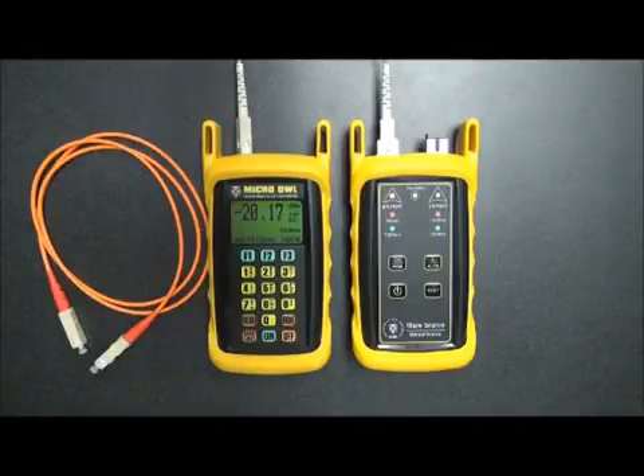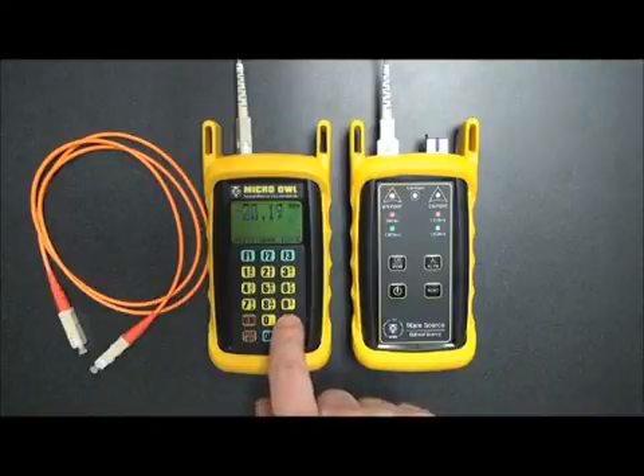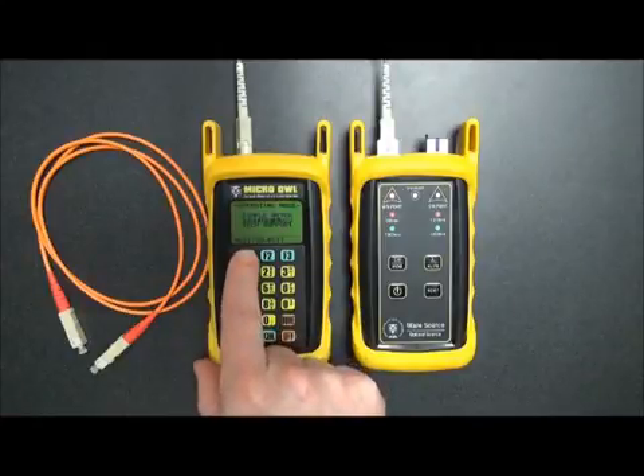Now that we've verified that our equipment and accessories are in proper operation, we can start the process of setting the meter up for the certification test. Now, if you remember from before, we were in Simple Meter. Simple Meter is not to be used for the link parameter setup. We need to be in certify link mode for that. If you remember the certify link mode from the operating mode screen before. So to return to the operating mode screen, we simply press the done key on the micro-owl to return to operating mode. Then we press F1 to move down to highlight certify link, and then we'll press F2 to select.